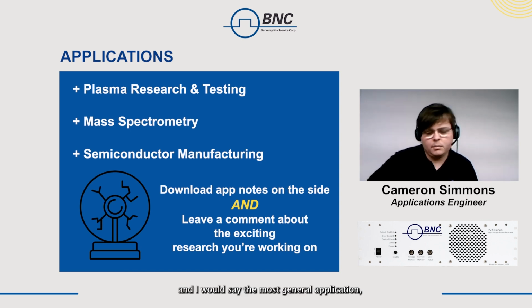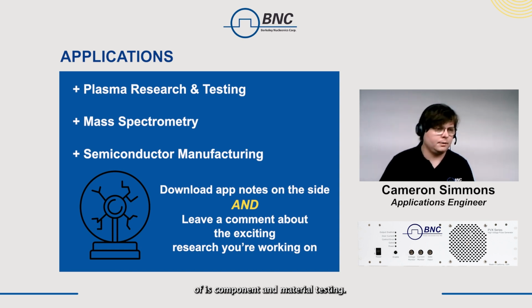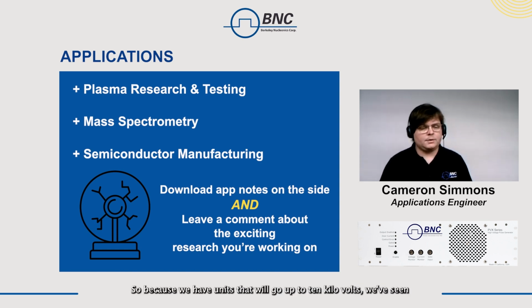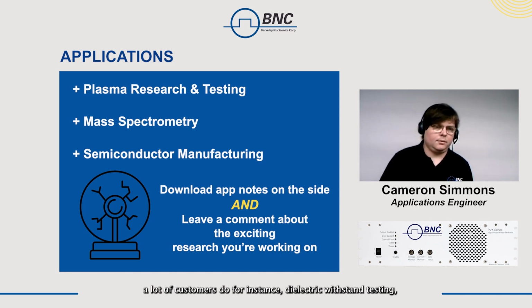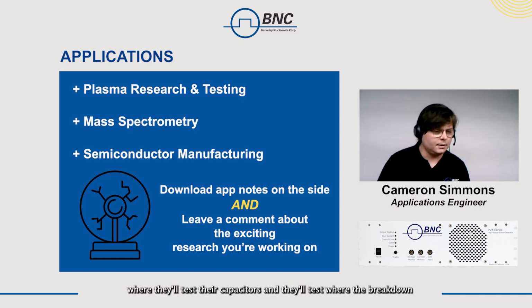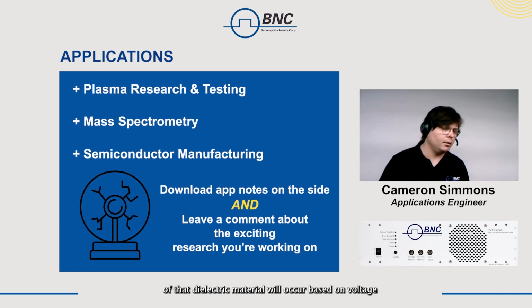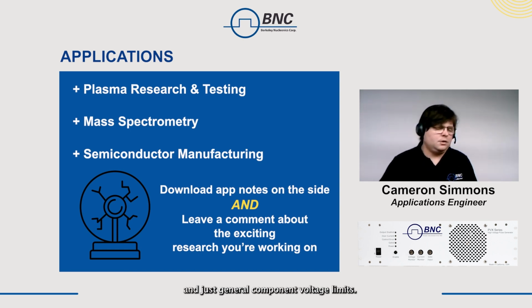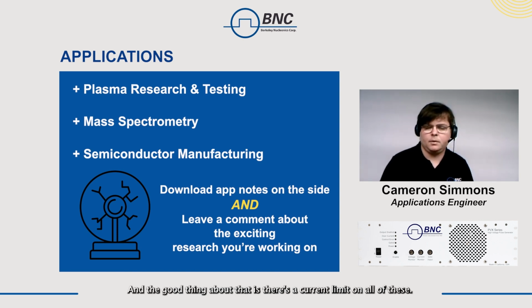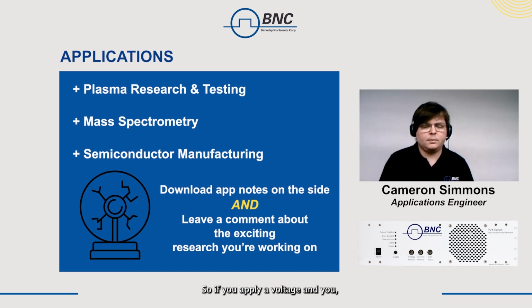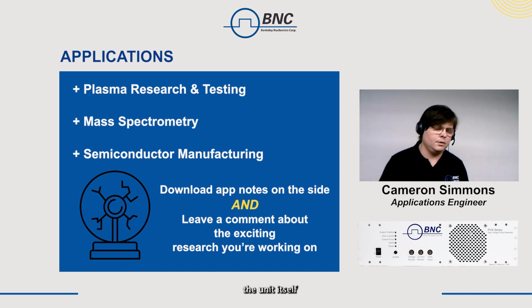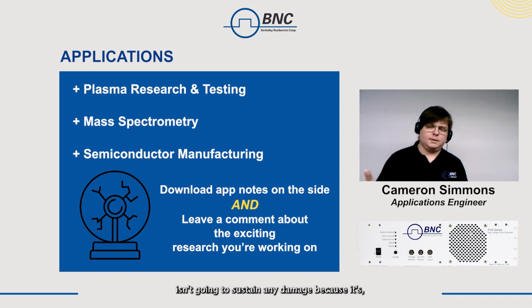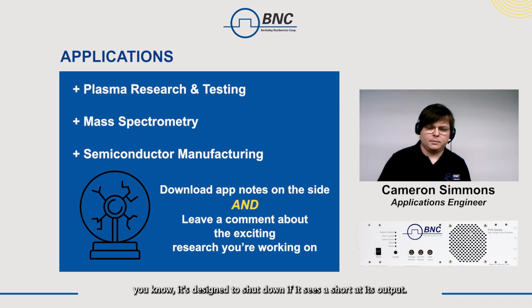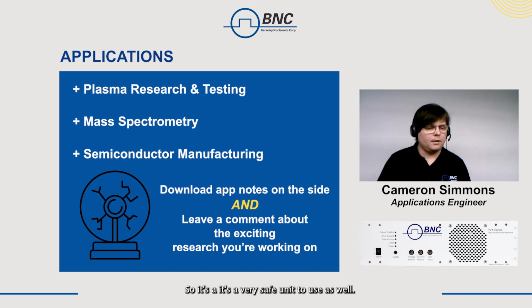I would say the most general application, but something we've really seen a lot of, is component and material testing. Because we have units that go up to 10 kilovolts, we've seen a lot of customers do dielectric withstand testing, where they test their capacitors and find where the breakdown of that dielectric material will occur based on voltage, and general component voltage limits. The good thing is there's a current limit on all of these, so if you apply a voltage and short your component, the unit itself isn't going to sustain any damage, because it's designed to shut down if it sees a short at its output. So it's a very safe unit to use as well.